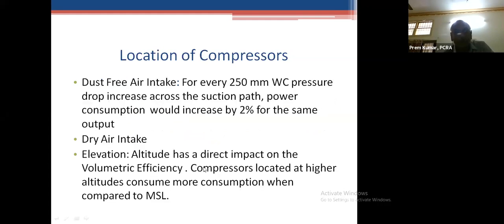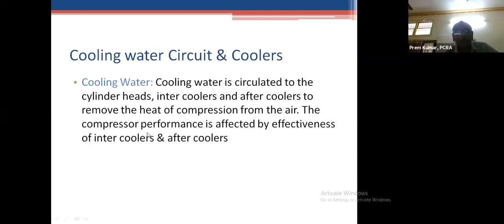The altitude is very important. Sometimes some companies resort to usage in the sister company. In one company in Chennai, a 200 CFM compressor was shifted to a company at Kunur. Without derating, they used it, and because the performance is poor, ensure this derating factor. So air should be dry. Cooling water is also an important factor. Where there are water cooled compressors, ensure that scaling is not there, and the water quality should be improved.